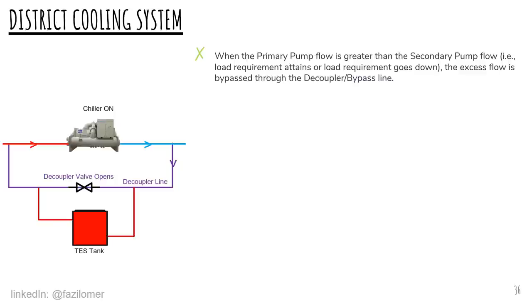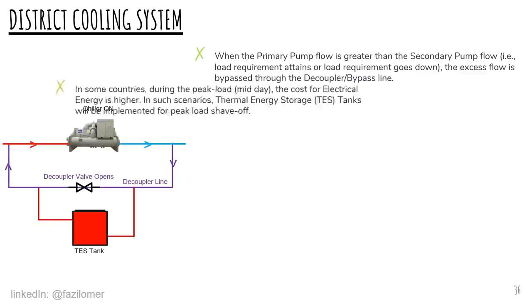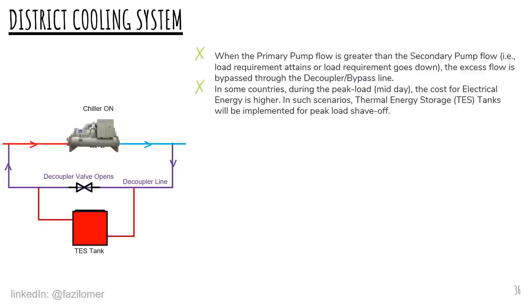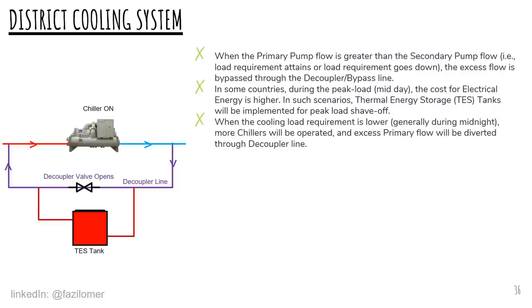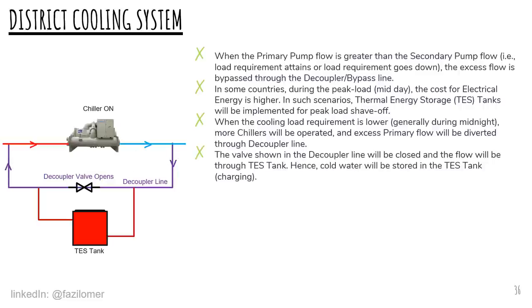In some countries, during the peak load, usually midday, the cost for electrical energy is higher. In such scenarios, thermal energy storage tanks will be implemented for peak load shave-off. When the cooling load requirement is lower, generally during midnight, more chillers will be operated, and excess primary flow will be diverted through the decoupler line. The valve shown in the decoupler line will be closed and the flow will be through the TES tank. Hence, cold water will be stored in the TES tank. This process is called TES tank charging.